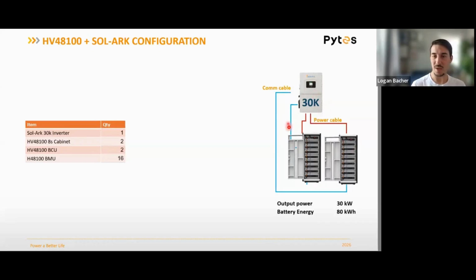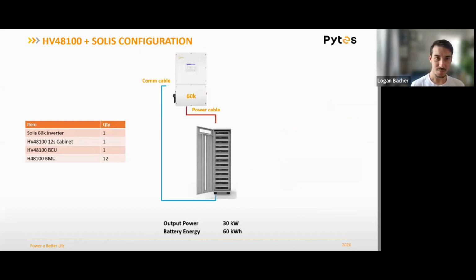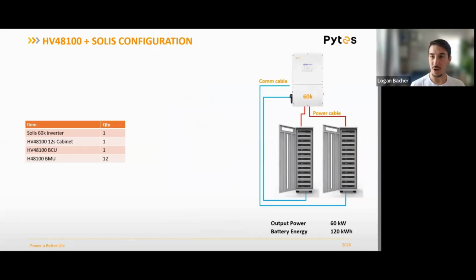But again, my main point here is how easy it is anytime you can stick to that 1-to-1 or 2-to-1 battery to inverter ratio. Anytime that's possible, I highly recommend doing that. So, a similar example with Solis, all that's changing is we're doing 12 batteries in series instead of 8, because again, the Solus has a slightly higher input than either of the Sol-Ark models. So the concept is identical.